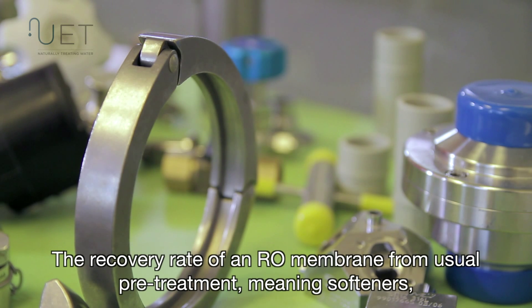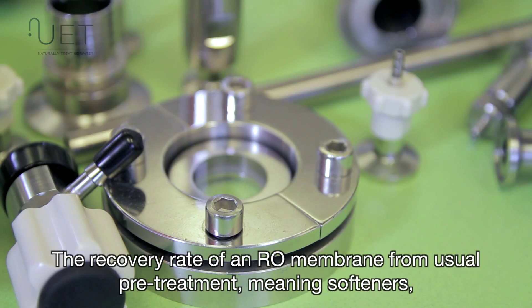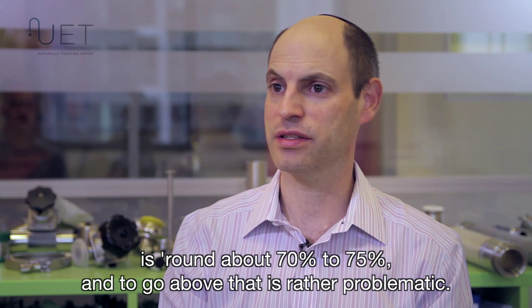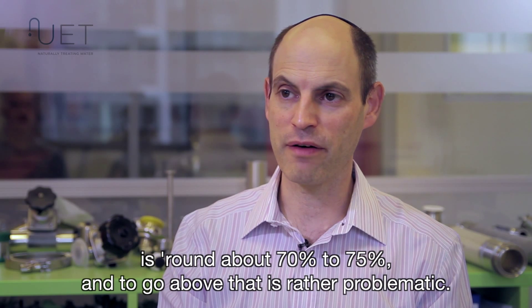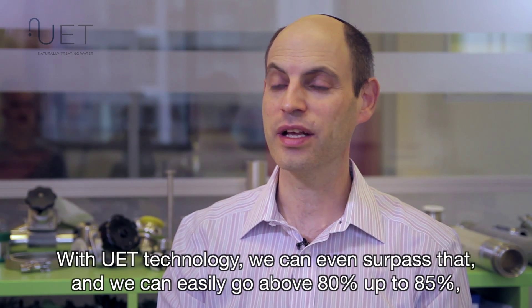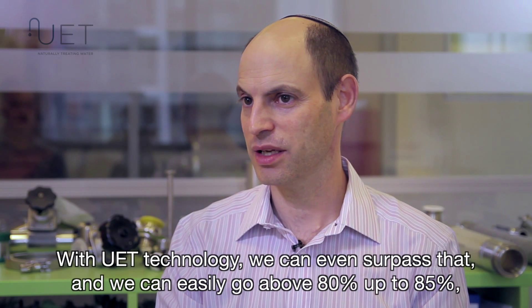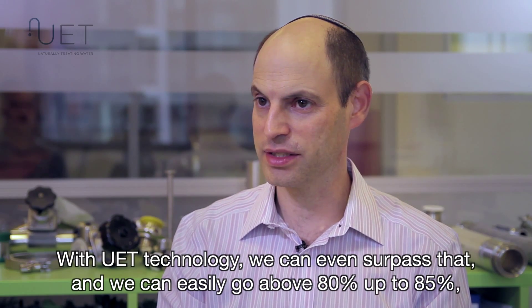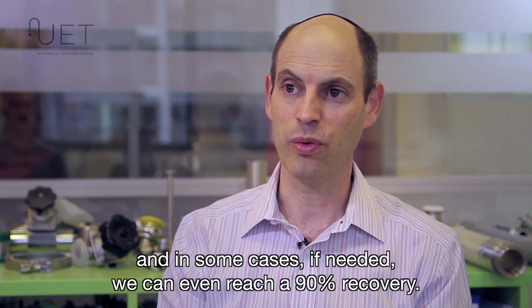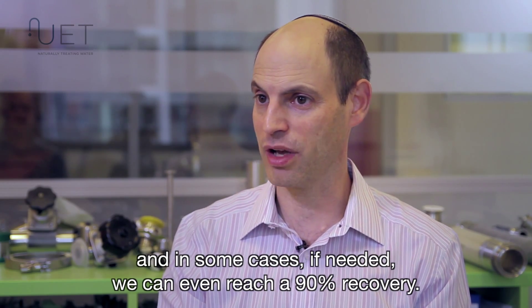The recovery rate of an RO membrane from usual pretreatment, meaning softening, is around 70% to 75%, and going above that is rather problematic. With UET technology, we can surpass that and easily go above 80%, up to 85%, and in some cases, if needed, we can even reach 90% recovery.